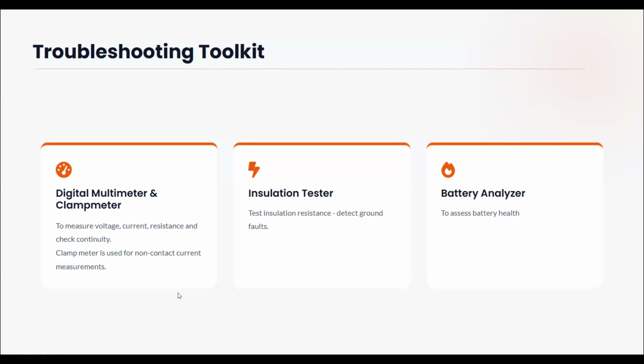And then it will show you the result without cutting the cable, without peeling the insulation or any physical contact directly with the conductor. So it will give you your results. You can measure from 0 point something milliohms to as high as 1,000 ohms, depending on the capacity of the instrument you have. The insulation meter helps to test insulation resistance and detect grounding faults.